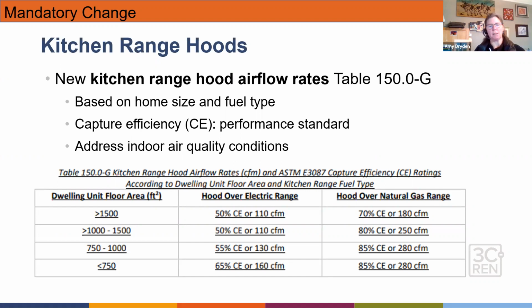One is the dwelling unit floor area and square footage on the left, so your CFM rate is tied to that square footage. And then the next two columns depend on whether you're using an electric or gas range. Now, the particulate matter from our cooking doesn't depend on my fuel source, right? If I burn something, I'm going to have that particulate matter either way. But we do see increased pollutants, in particular NOx, coming from gas stoves.